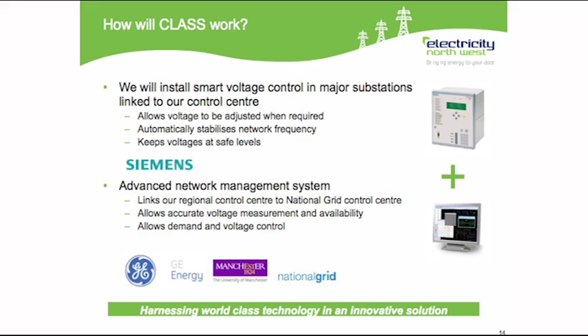Now, the key thing is this project is all about fitting intelligent control gear to existing main power system assets. It's not about putting large high capital value assets onto the system. So in the primary substations, which is where we regulate the voltage from 33 kV down to 11,000 volts, we will install new smart voltage control relays, which will be linked in real time to our control centre in Manchester. And they are really the brains of the system that allow us to adjust voltage on the network by very small increments whenever required, and to do it in a coordinated manner to provide the services, either voltage boost, voltage decrease, or frequency response that I've talked about before.